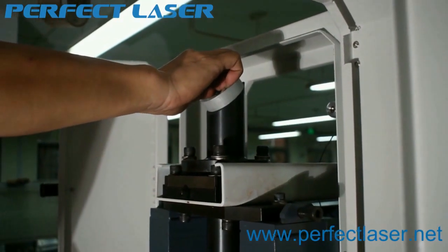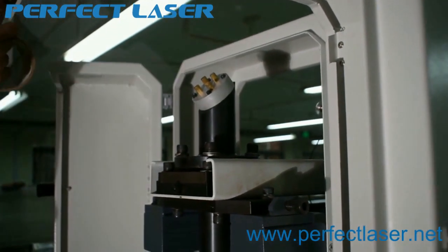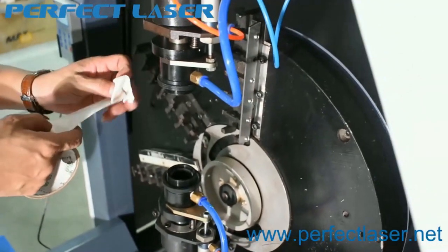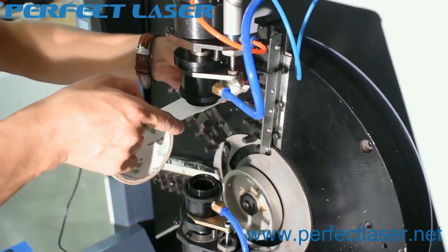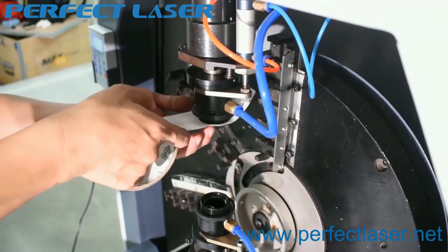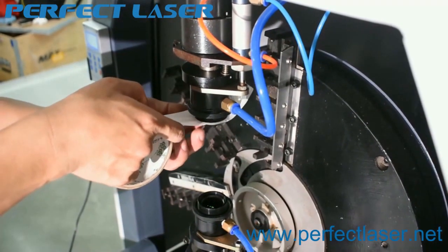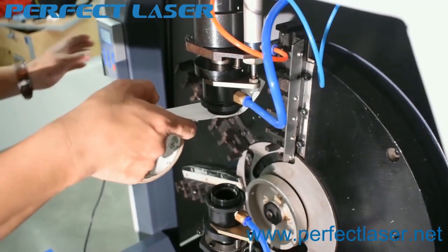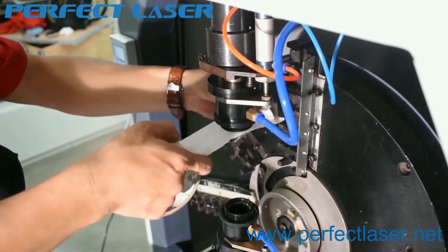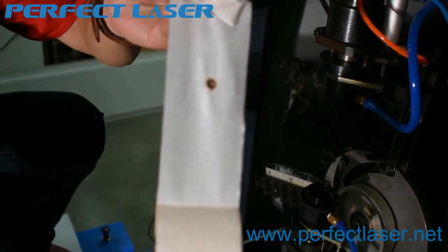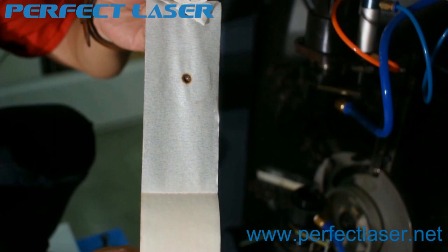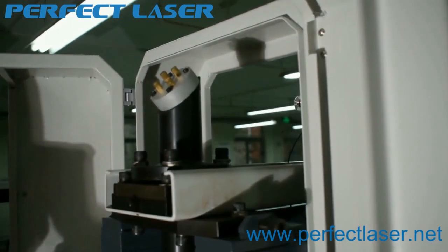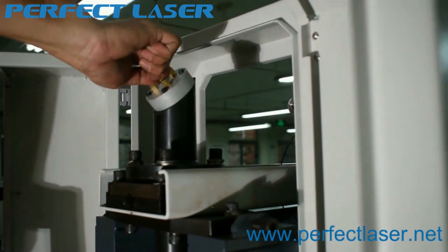So we need to align again. We just align a little, it's okay. And we test again. This is how to align the laser path, because we have to make sure all the laser comes out in the center of the mirrors. Okay? Now it's in the center of the circle, so we finish this step. And to fix this laser beam, fix the center screw. So the laser beam has been fixed.